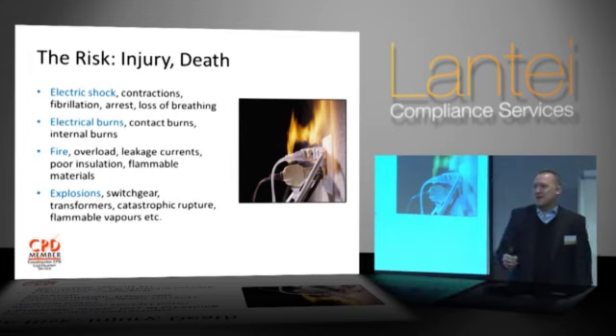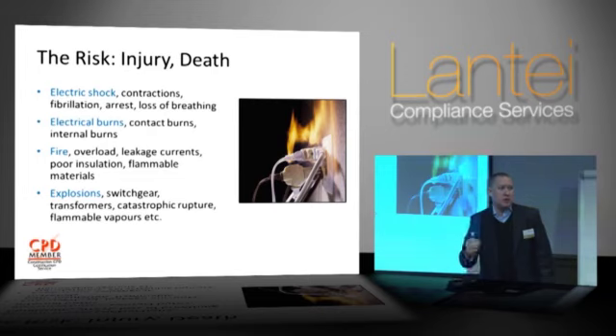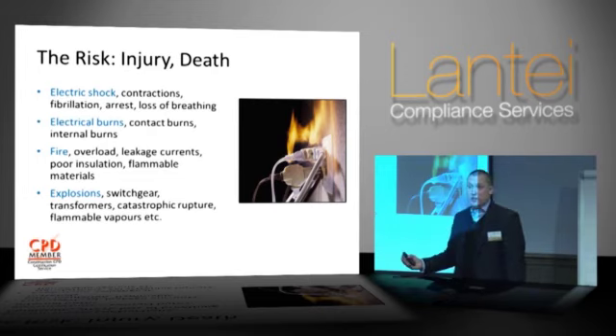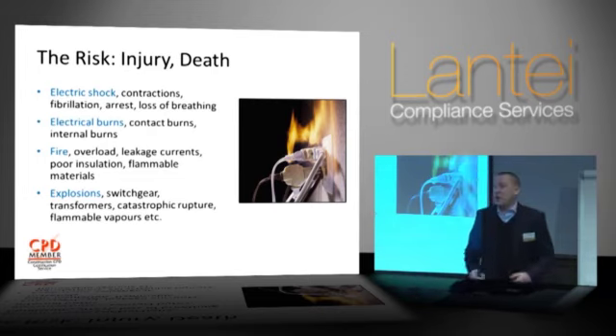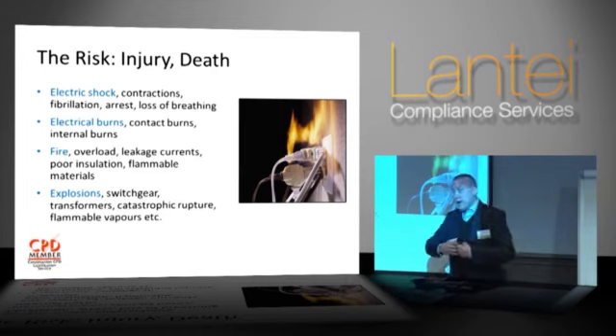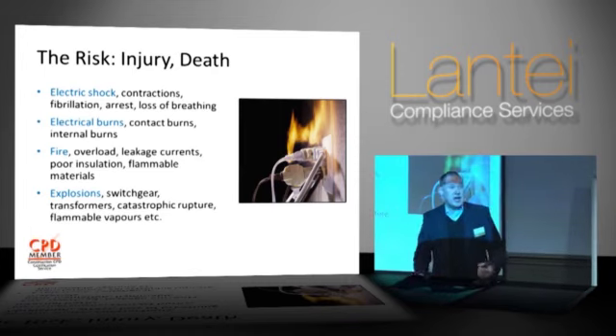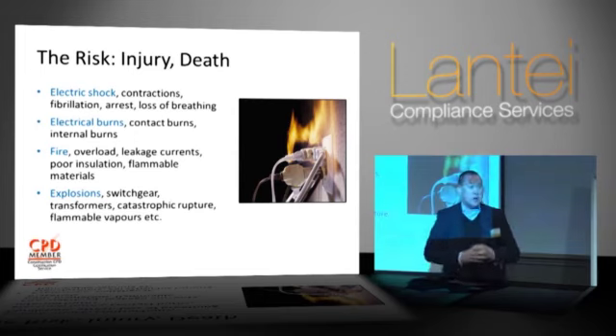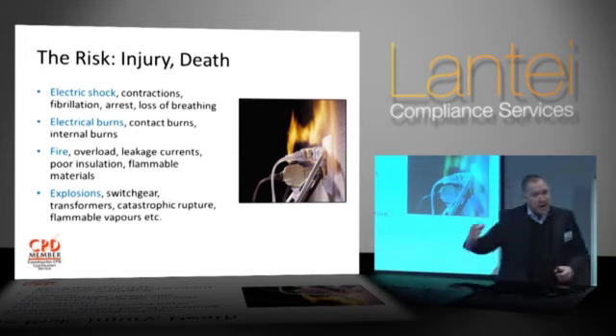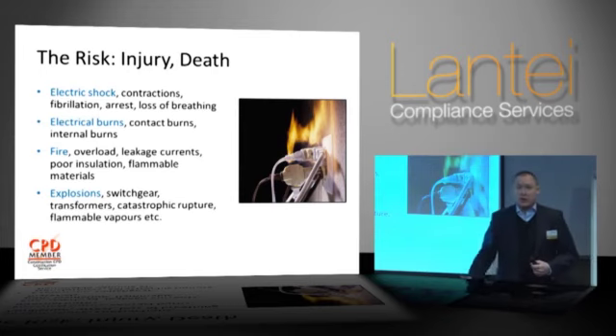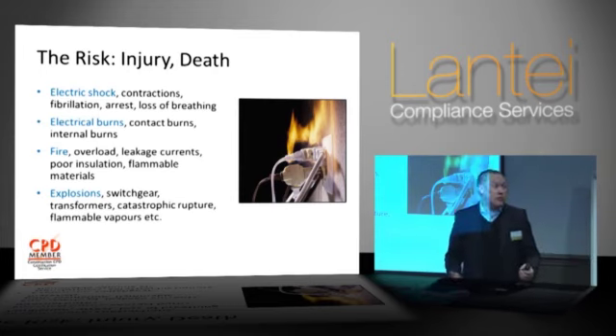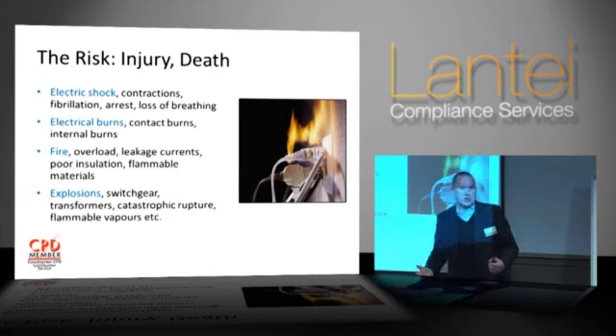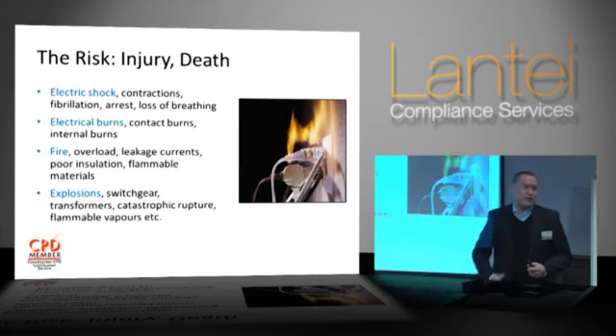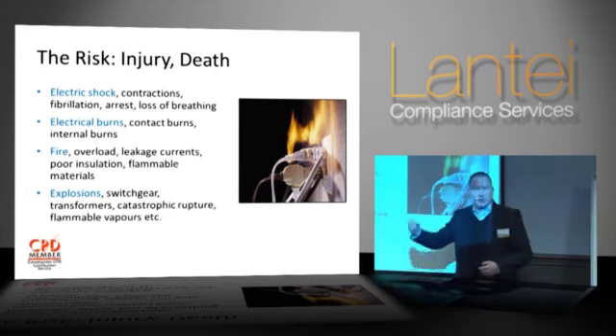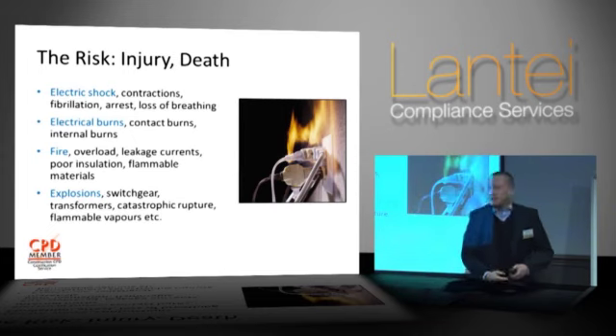Don't underestimate how big a challenge we've got in the modern built environment with leakage current issues. For those of you who might not be aware, leakage currents occur naturally because of the design and makeup of pieces of equipment, and this applies to many types of equipment we now connect to electrical systems. Naturally, we get currents on the protective conductor, the earth conductor. Well, clearly that doesn't sound very good, does it? But it's a natural phenomenon now, and what we've got to be able to do is identify it and protect against it.